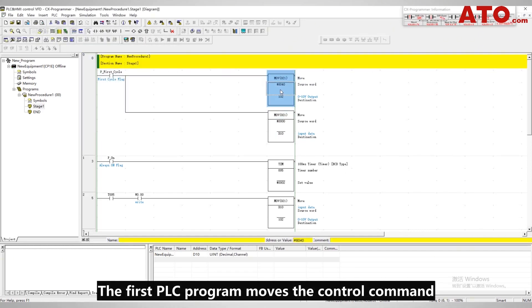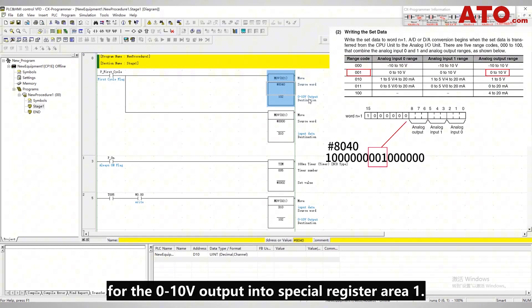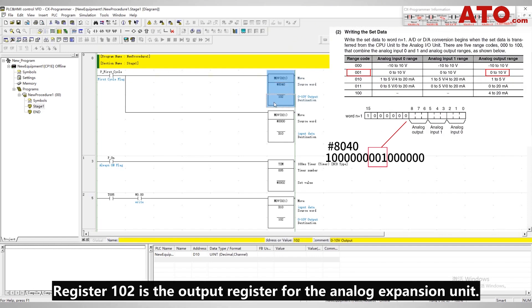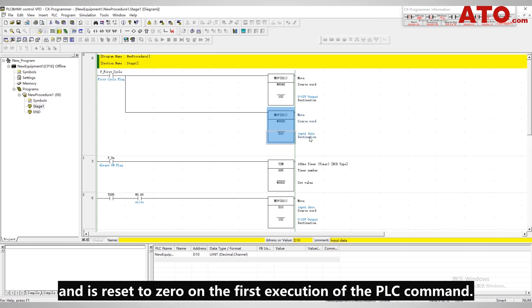Let's delve into the PLC programming specifics. The first PLC program moves the control command for the 0–10 volts output into special register area 1. Register 102 is the output register for the analog expansion unit. D10 stores VFD input frequency data and is reset to 0 on the first execution of the PLC command.